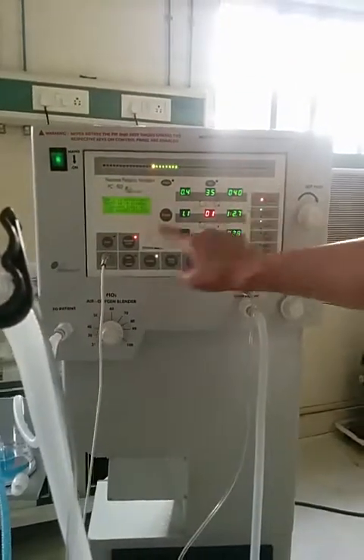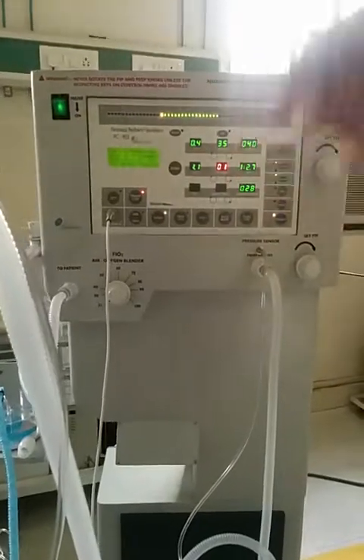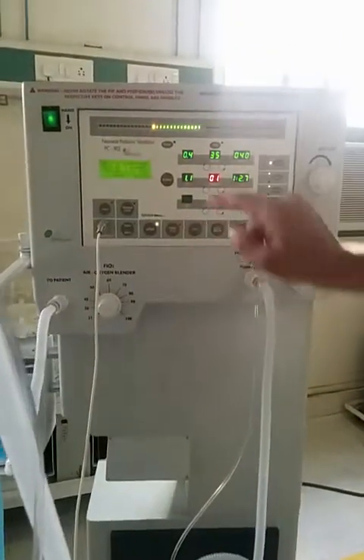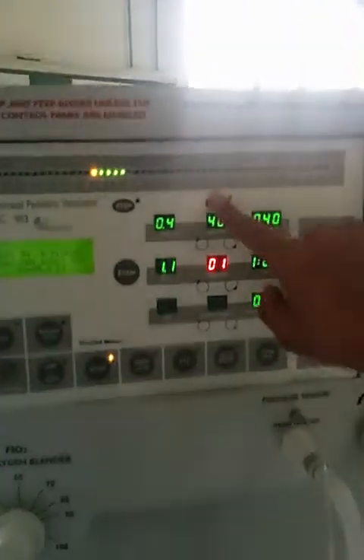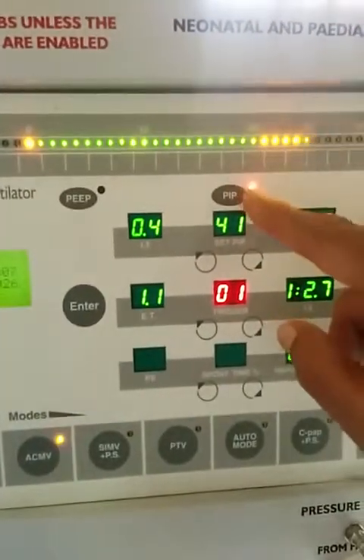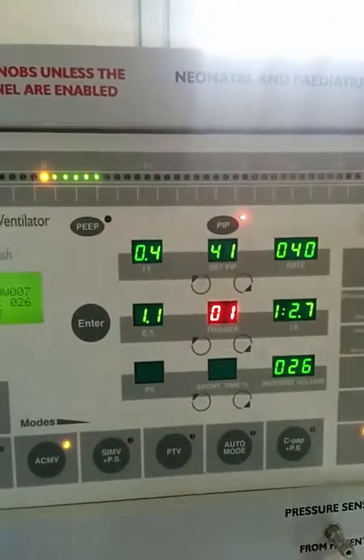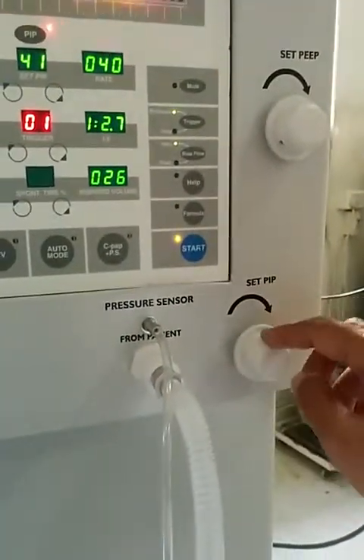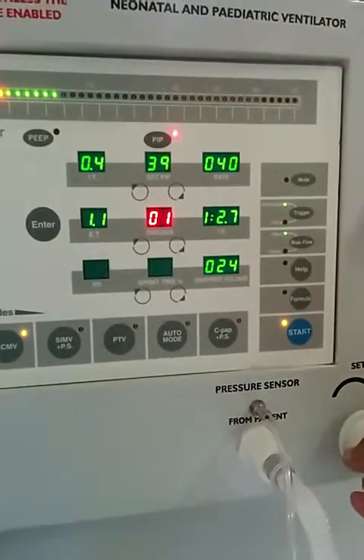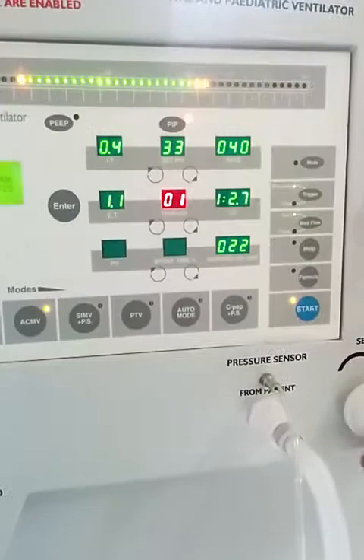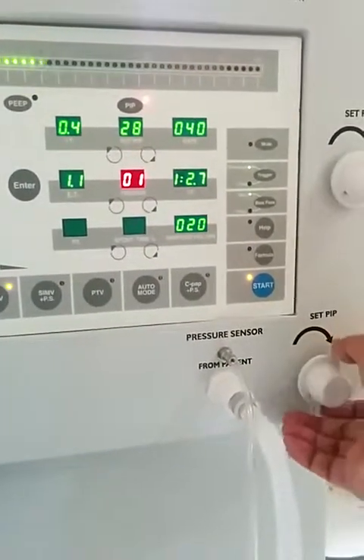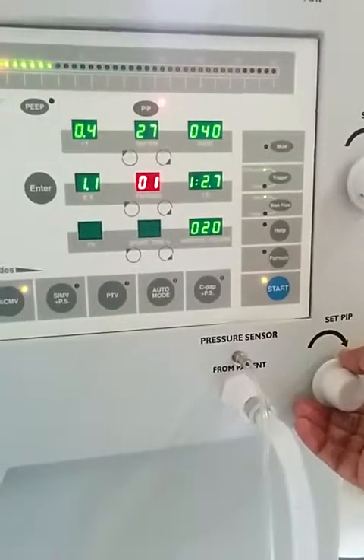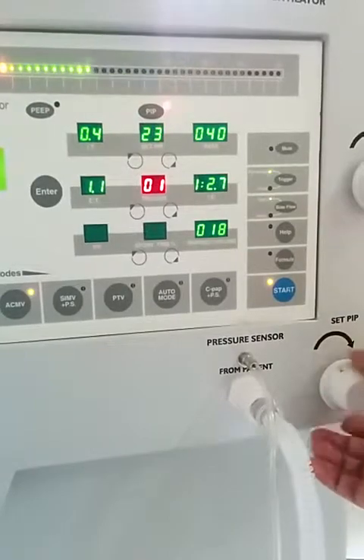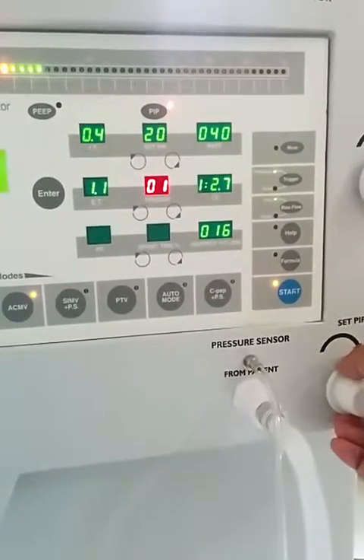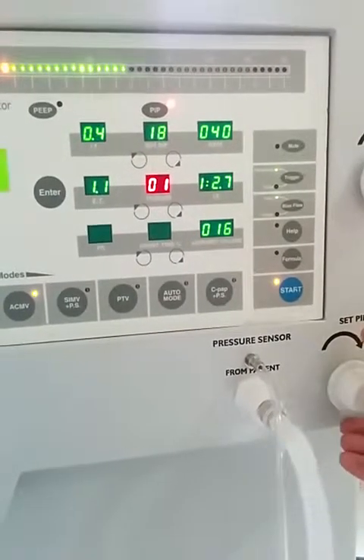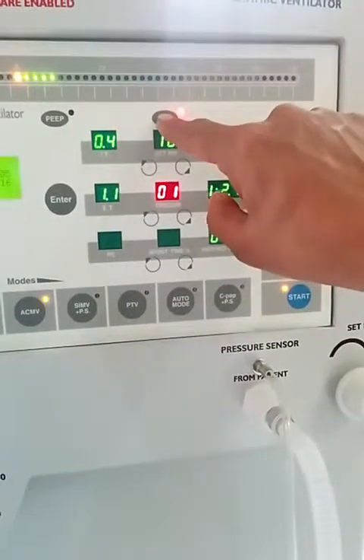So now I start the machine, and the machine is working and automatically the keypad is locked. To set the peak inspiratory pressure, I will open the keypad and press the PIP key. Once the key is pressed, it will be indicated by a light emitting diode. Now by using this knob, you increase or decrease the peak inspiratory pressure, which will be displayed on the LED display. As I've told, we are setting it for a newborn baby. We have set an inspiration time of 0.4 second, a rate of 40, a PEEP of 4. So I will set a PIP of 18 centimeters of water column. Once I've set it, I will acknowledge it by pressing the PIP key.